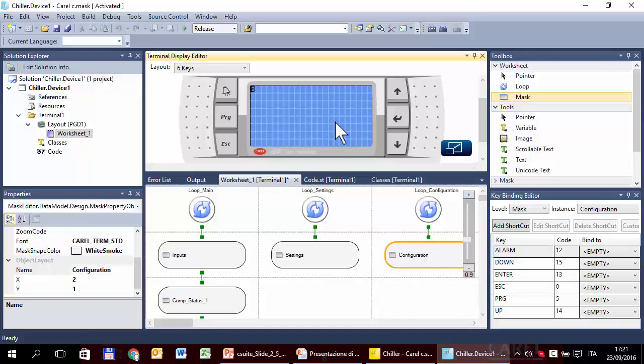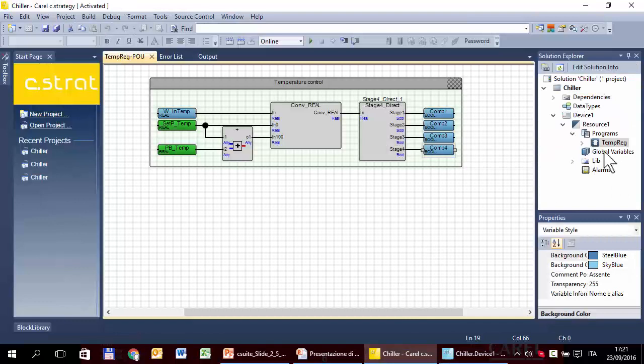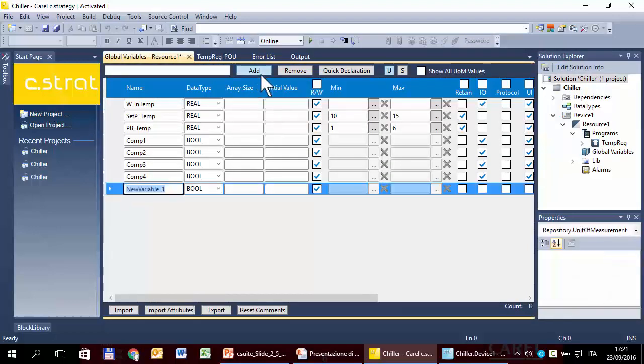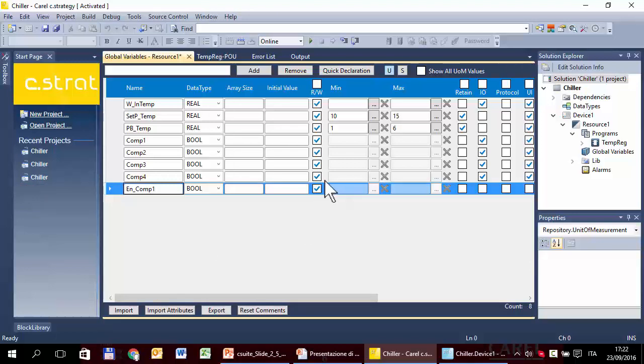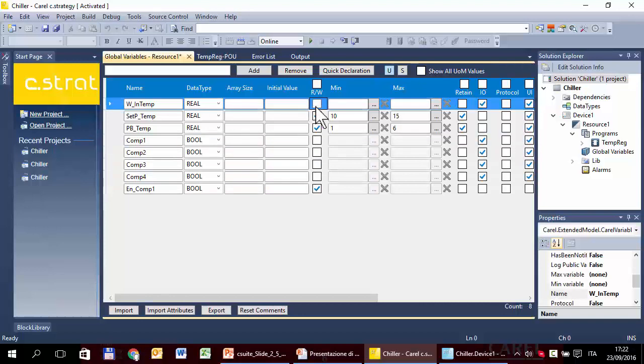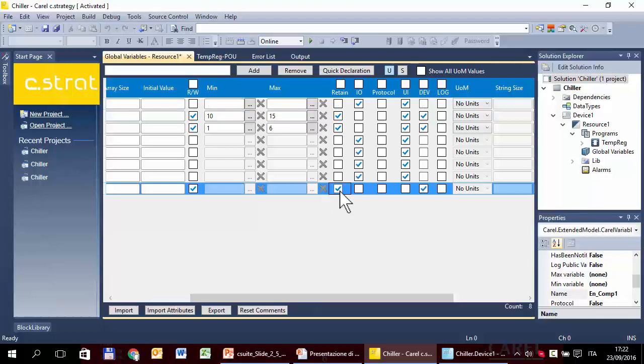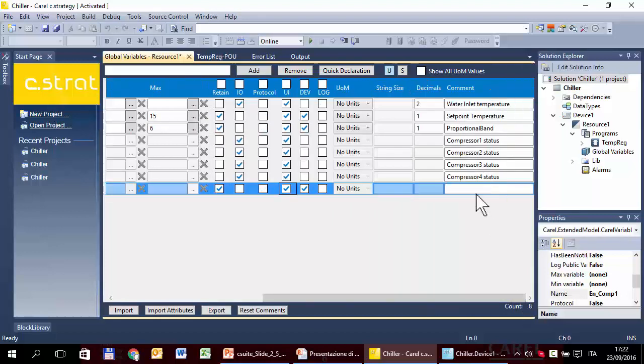So we can create the variables. Go back in the strategy, in the global variables, and create a new variable. Boolean is good. A good name is 'Enable Compressor One.' Read-write is correct, because we want to change the value in the mask and maybe also in other editors. Retain — yes, because we don't want to lose the selection after a blackout. And visible also in the UI, user interface.